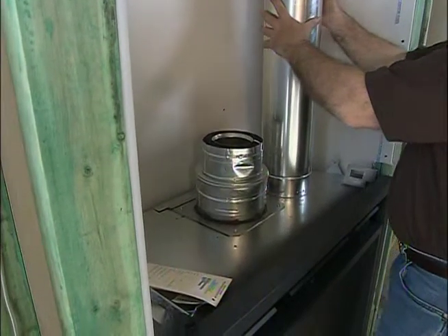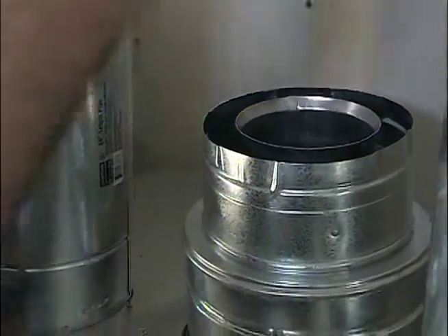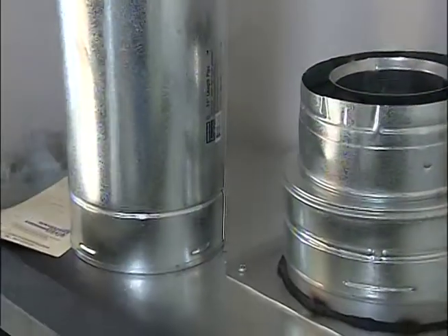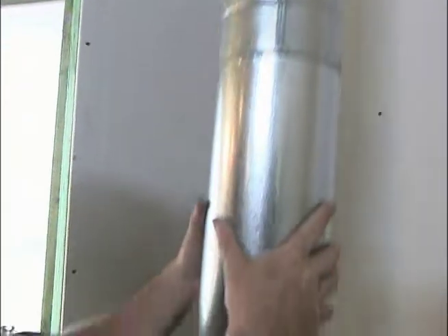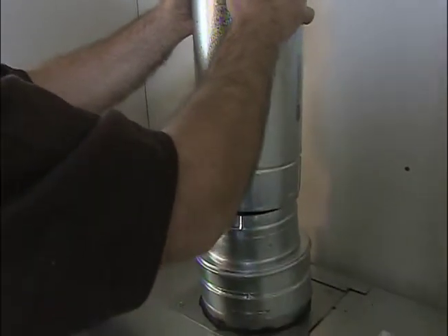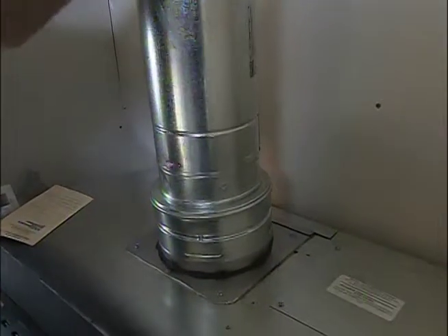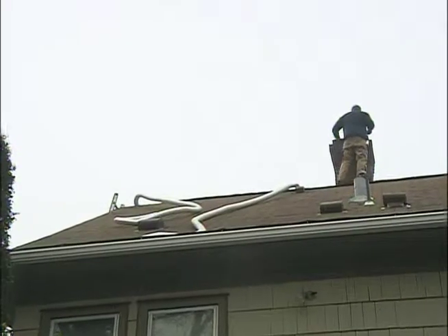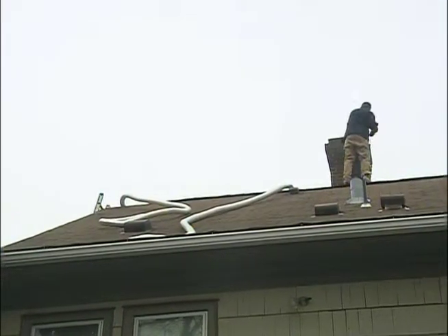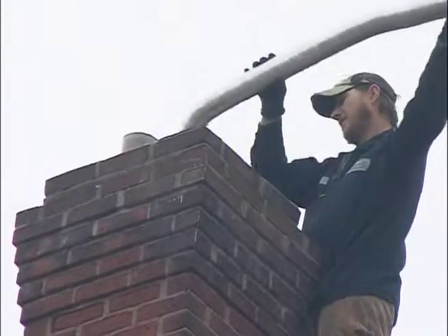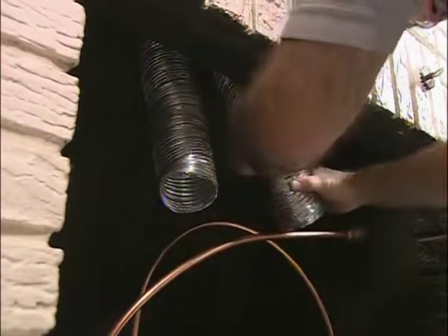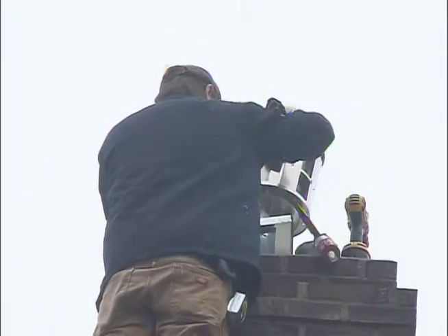Again, with the gas fireplace, it uses a coaxial venting system, a vent within a vent. That inside vent is an exhaust vent, and the outside vent is the intake. And by doing it that way, you're able to frame within a short distance of that venting system. Whereas with a gas insert, there are no combustible materials around it, so they use what they call collinear venting systems. So we drop a couple of liners down through that existing chimney system. One's an intake, one's an exhaust liner. And we attach those to a cap up at the top of the chimney.